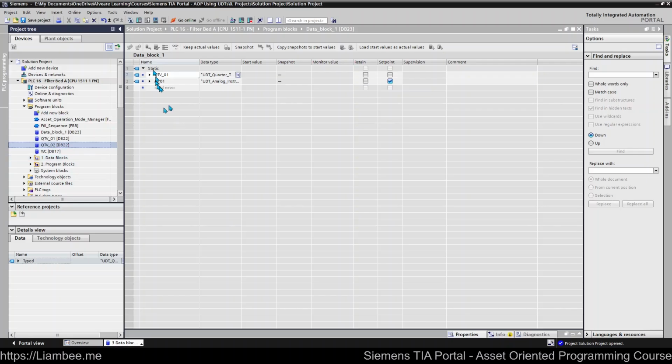If you go down the road of putting stuff together, you need to understand that if you make changes to any asset that appears in that data block, you're going to affect the data for other assets. And I know that we can activate memory reserve in optimized data to sort of preserve that and help, but you have a limit on that. And if you've got lots of things in here that are all wanting to change, then you'll find that you'll eat up that memory reserve quite quickly, and it might not save you anyway. So it's better to have multiple blocks, multiple instances of your UDT, than have them all bundled together.